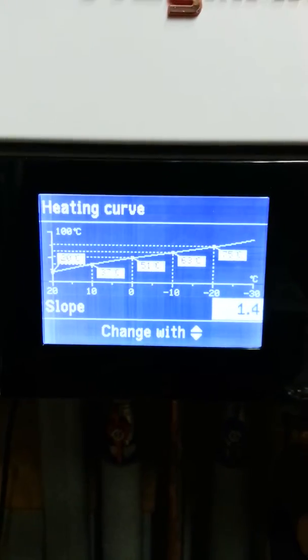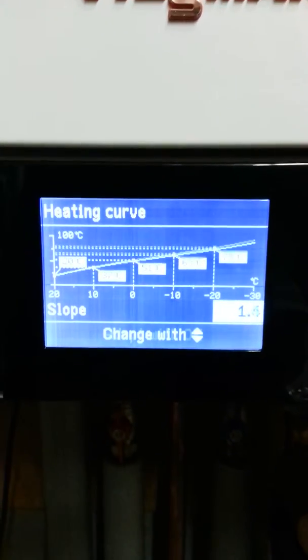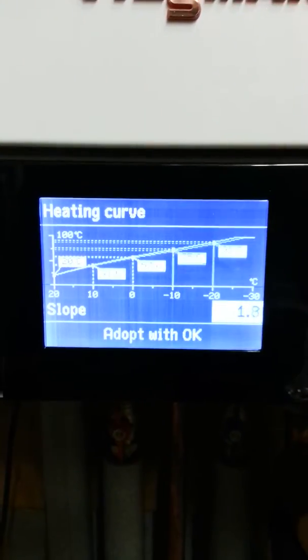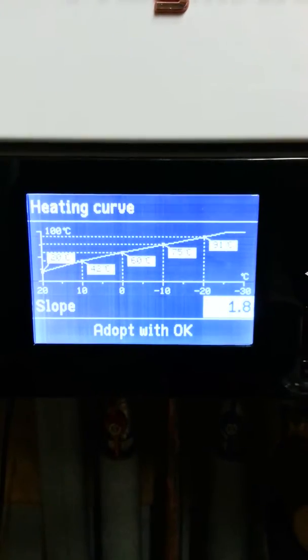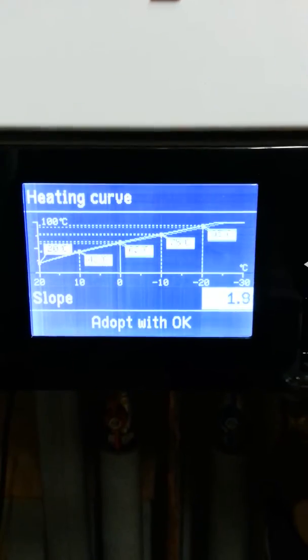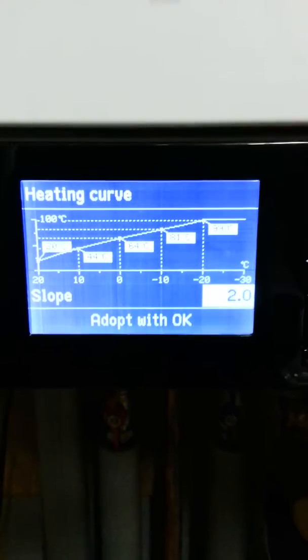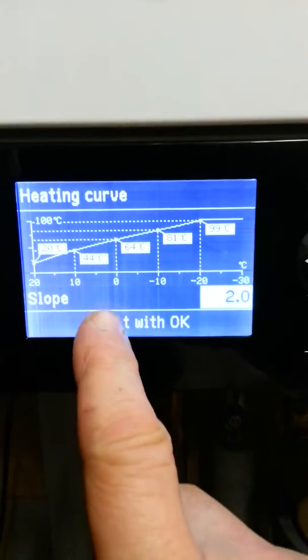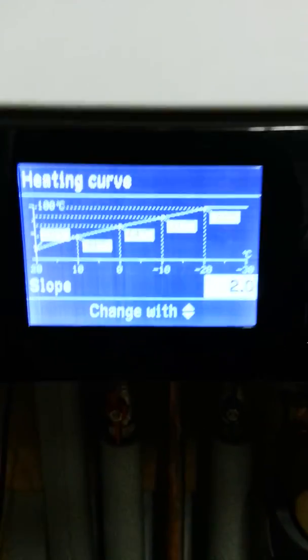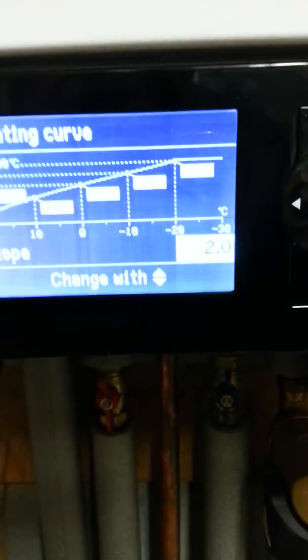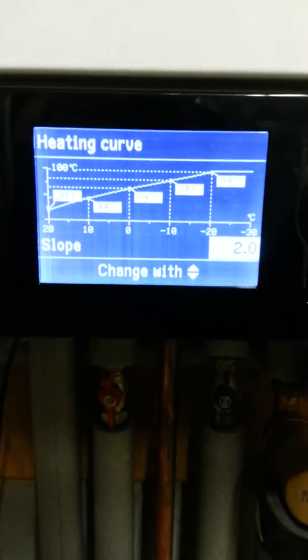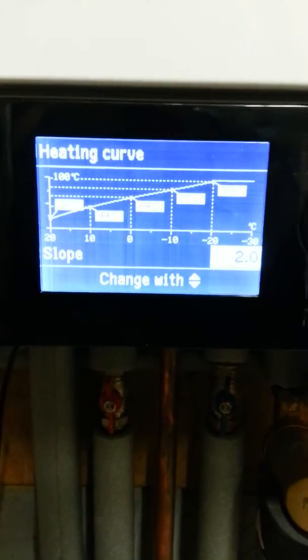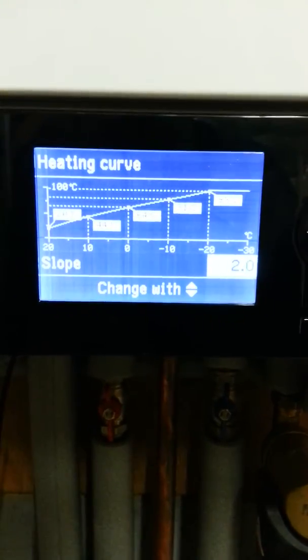Very often for old Victorian terraced houses, to give you some kind of idea, somewhere between 1.8 and occasionally as high as two. So here you can see at zero degrees outside, we would have to run up to, I don't know if you can see that in the video, we'd have to run up to 64 flow.